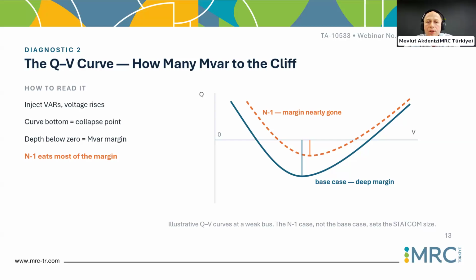So in order to keep this curve shifted up, sometimes fixed capacitors may be a solution, but fixed capacitors only shift the curve. We also want to reshape the curve by adding some dynamic reactive compensation, which brings some reshaping of the curve, so we can shift the point, so we can increase our reactive power margin in case of an instability transient event in the real-time operation of the grid.